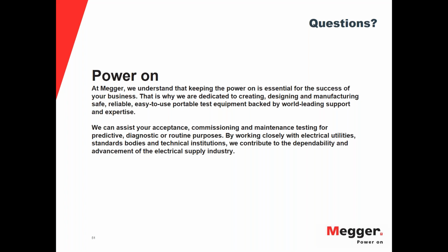So yes, the charger can be used to support the substation or the facility when the battery is not there, but then you're risking that if something happens, if there is any power failure, you're going to lose the charger and you're going to lose the facility because there's no battery to support that. So that's when the need for the backup battery comes in, depending on the criticality of your installation, or if you definitely cannot have the load without any power, you don't want to risk that. So you want to install a temporary backup.